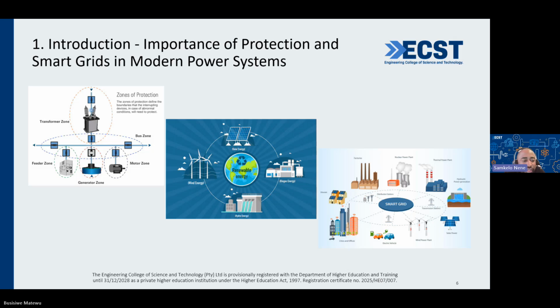However, if the system is faulty, or if the protection is not well coordinated, you'll find that even though there is a fault in the transformer zone, perhaps a circuit breaker in the motor zone will respond - that is miscoordination. So in essence, each and every zone has a primary protection system which is supposed to respond. If that doesn't respond, based on the relay setting, then a secondary protection system - in this instance, perhaps the protection system of the feeder - will then respond as the secondary or backup protection system. So I'm not sure if that's clear.